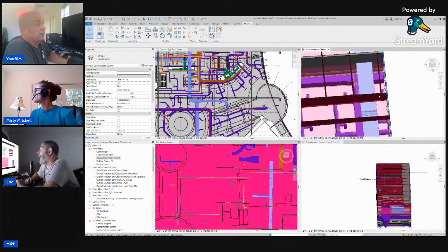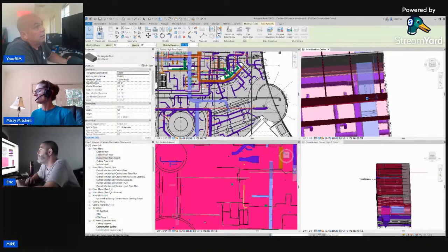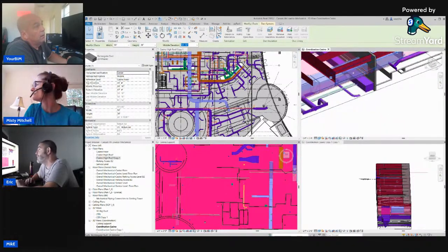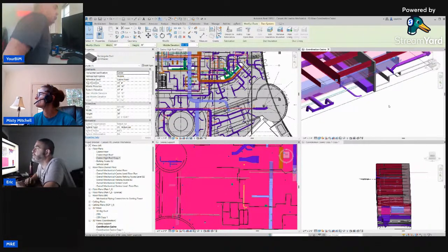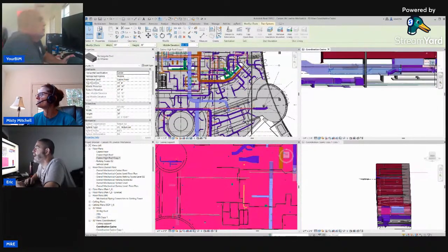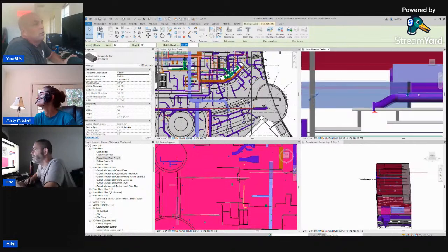And you will see, unfortunately, with these returns, some of them, when I get pushed up into the pocket, the little 4-inch outlet return that's going to the open air space is now up beside the steel beam. And I don't know how well that works. Well, they'll just have to do some kind of bottom diffuser or something like that. Okay. That's kind of what I figured.